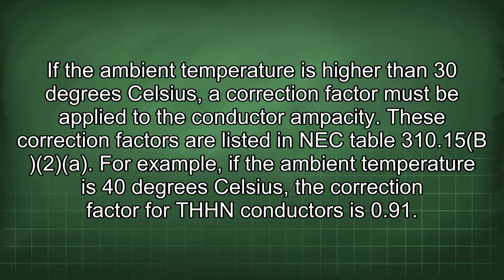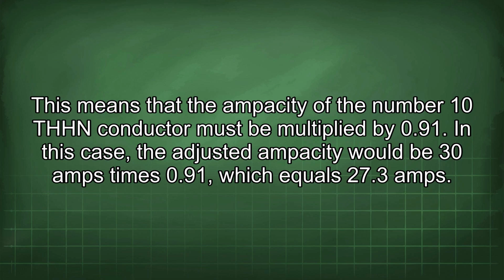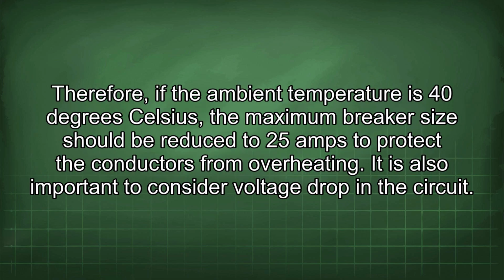the conductor ampacity. These correction factors are listed in NEC Table 310.15(B)(2). For example, if the ambient temperature is 40 degrees Celsius, the correction factor for THHN conductors is 0.91. This means that the ampacity of the number 10 THHN conductor must be multiplied by 0.91. In this case, the adjusted ampacity would be 30 amps times 0.91, which equals 27.3 amps. Therefore, if the ambient temperature is 40 degrees Celsius, the maximum breaker size should be reduced to 25 amps to protect the conductors from overheating.